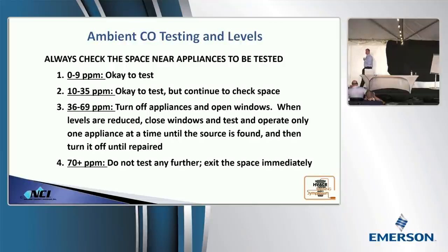Ideally, we should breathe 0 parts per million of CO. Depending on the equipment that's inside the building, especially if you're dealing with gas ovens, you may measure some ambient CO. So at 0 to 9 parts per million, it's okay to test. You're not in harm's way yet, but you need to find out why. Why is there CO inside that space? Continue to test, figure out where it's at. It may be the oven that's been running and you just need ventilation. Or there may be a deeper problem that you need to look into, such as we're going to talk about this morning with combustion air.